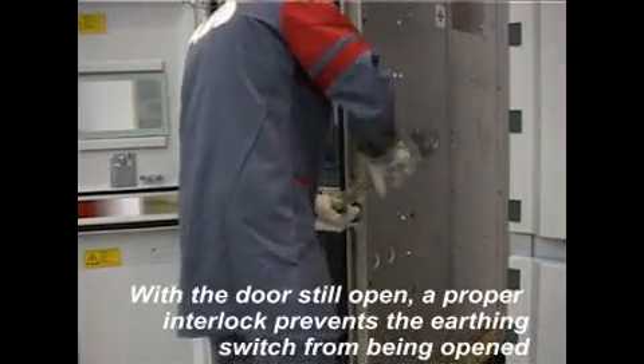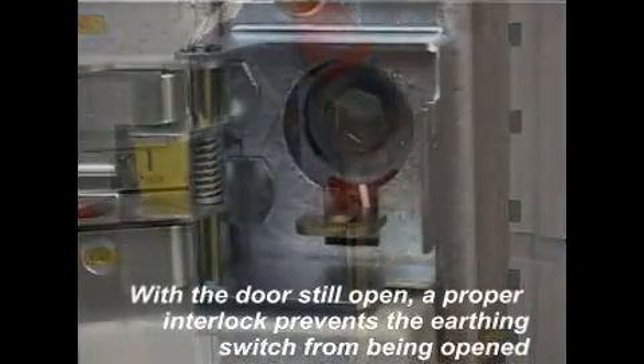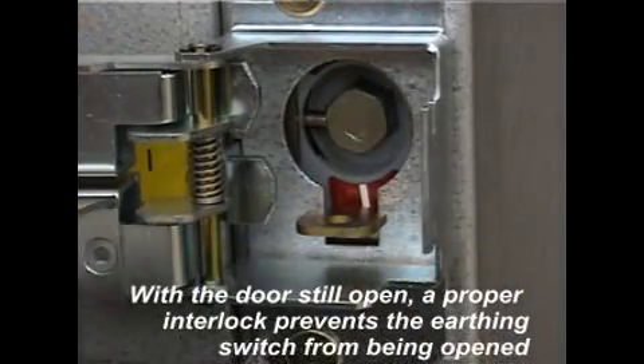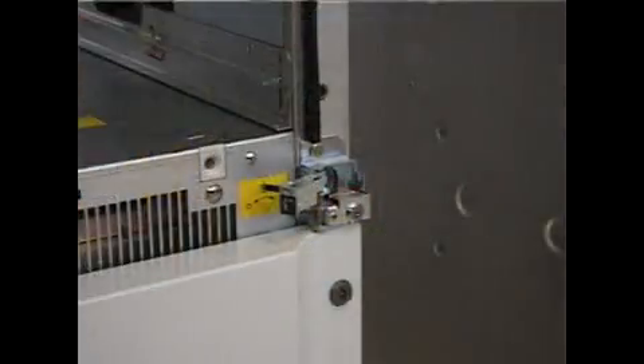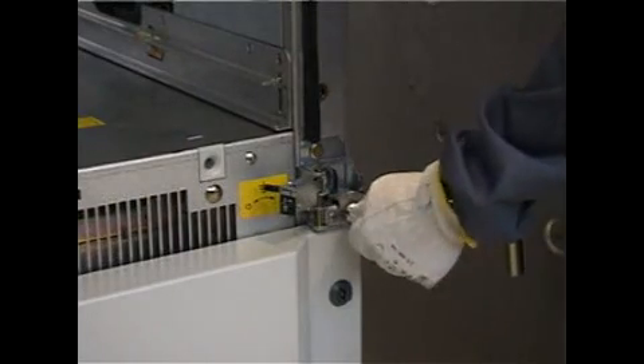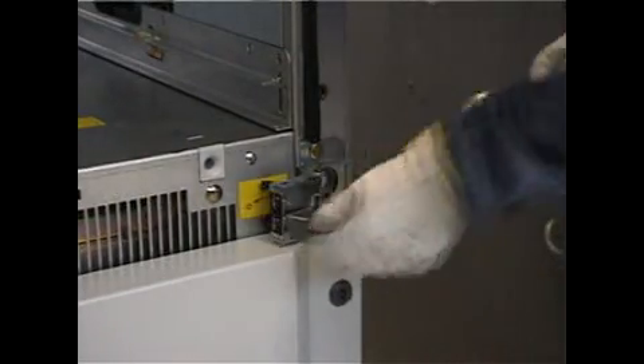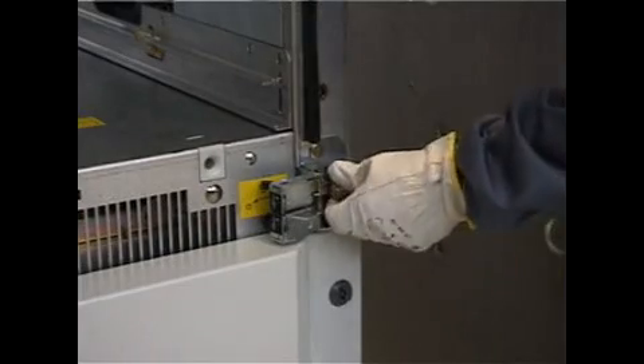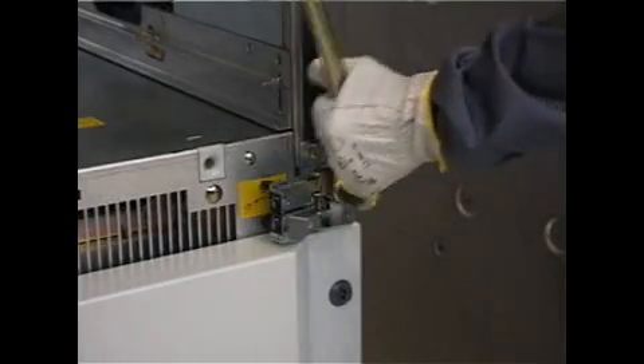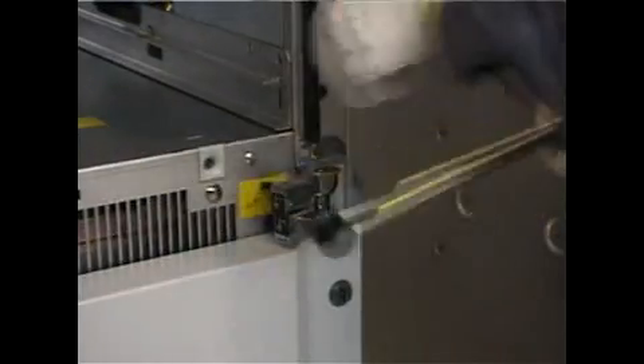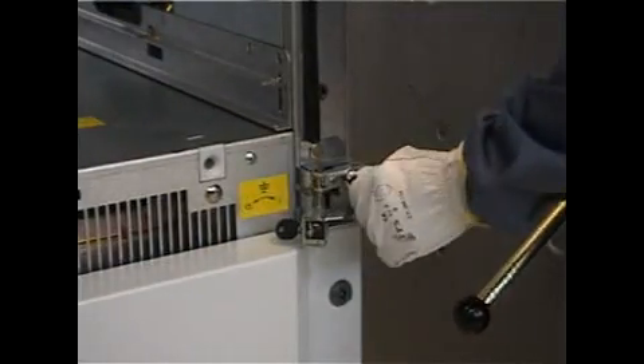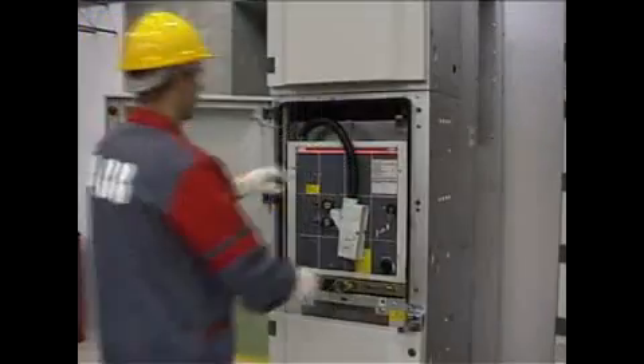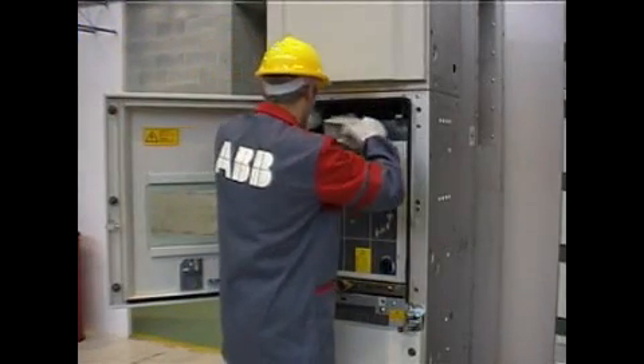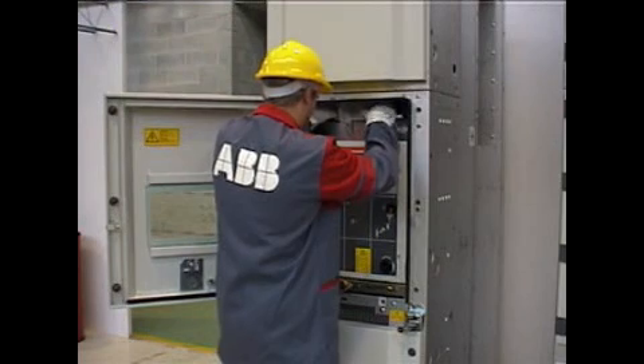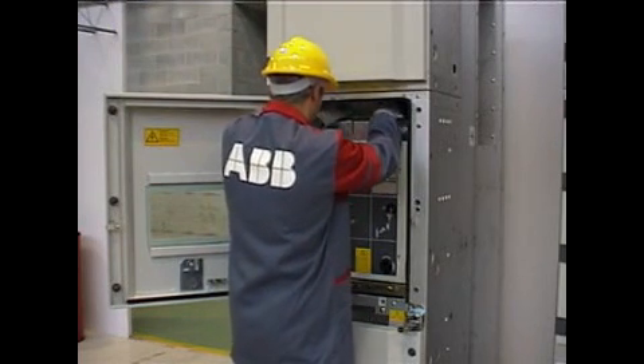An additional safety lock prevents the earthing switch from being operated while the door is still open by obstructing the access to the shaft. Now we can close the door. Insert the key to be able to open the earthing switch, open the earthing switch and operate on the key lock to prevent anybody from closing it again. We can now insert the breaker and then reconnect the auxiliary plug to have the breaker ready in test position.